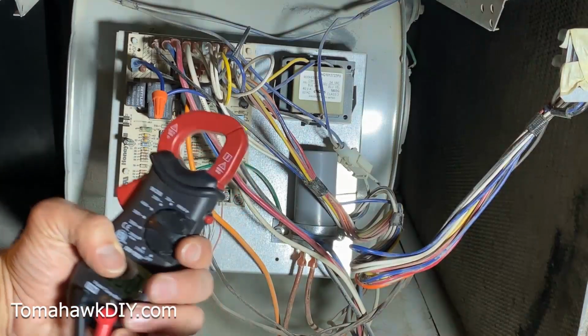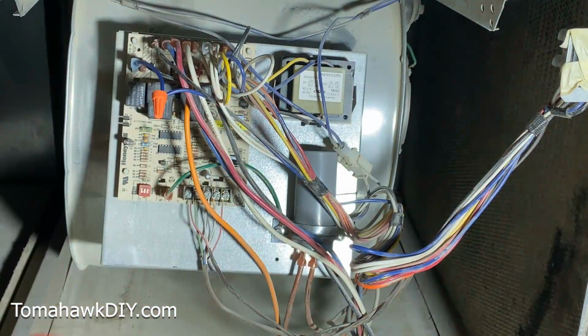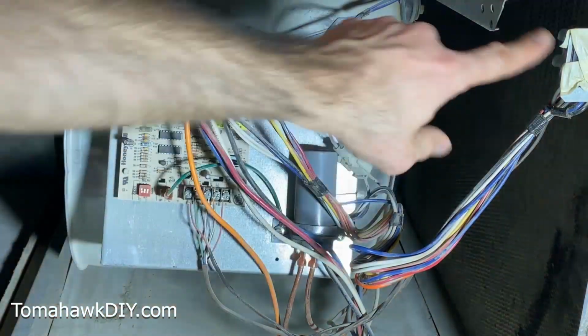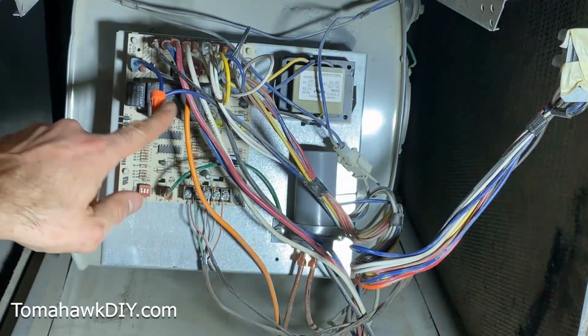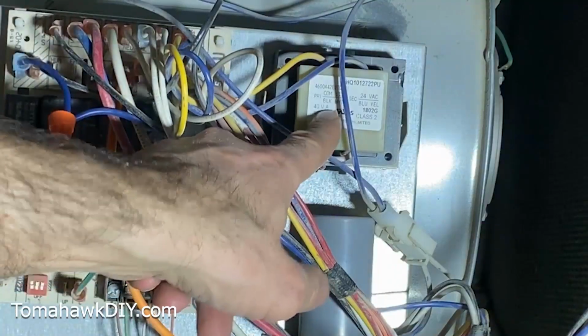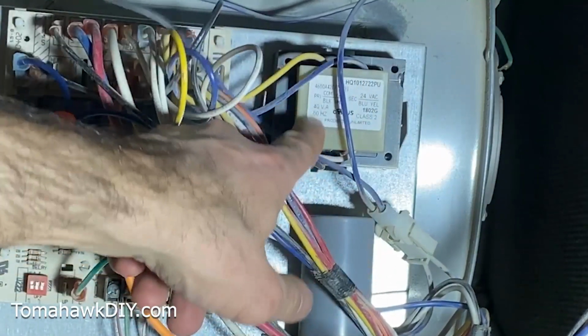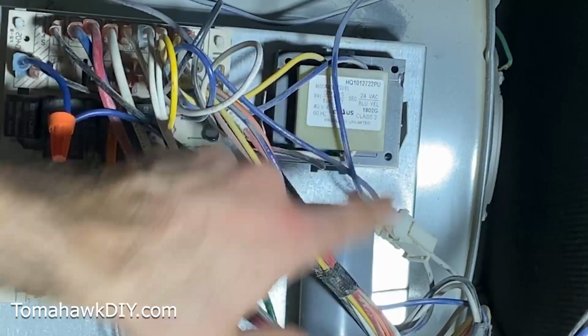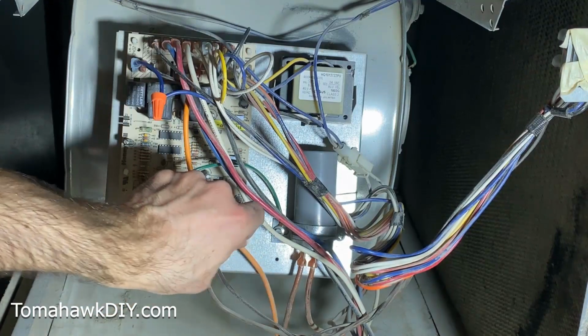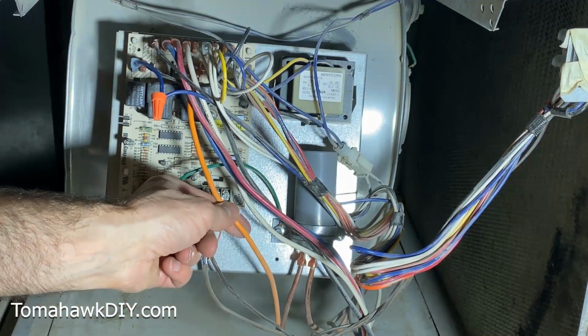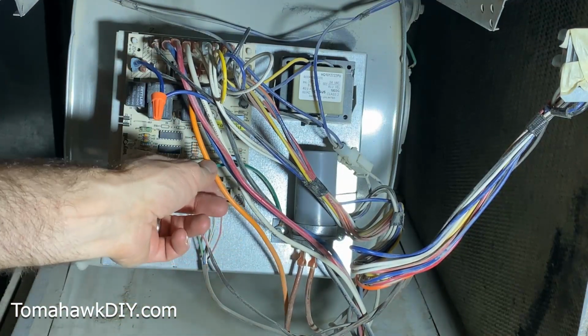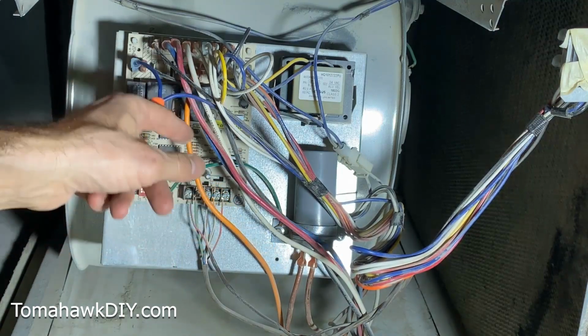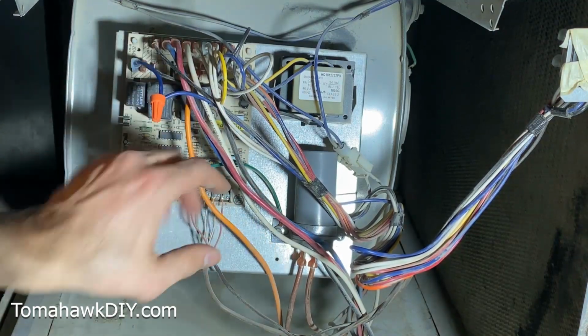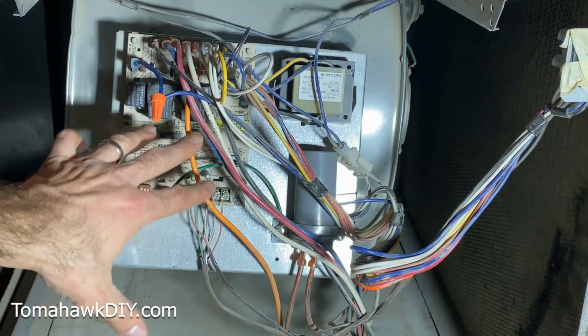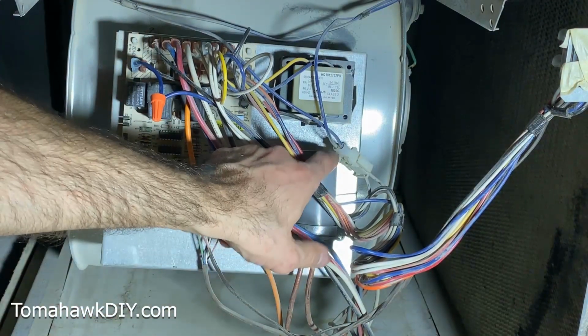Word of Advice TV really walks you through everything you need to know with your multimeter to check power coming into the board, going through the transformer, coming in one side at 120 volts on this furnace, coming out at 24 volts to the blower fan, which is where I discovered that this orange wire did not have 120 volts coming out of it or coming from the control board to it. So there's something that seems to be fried on the control board.